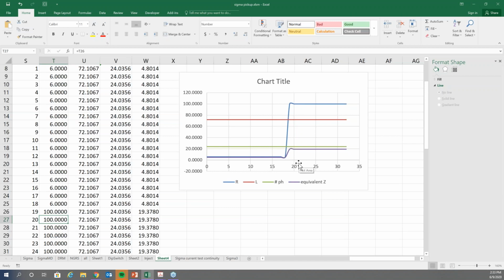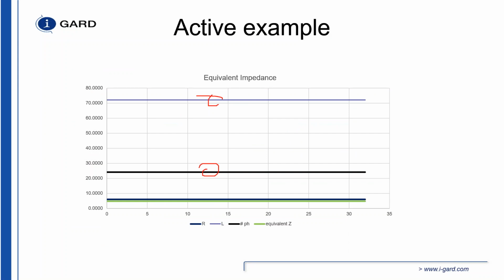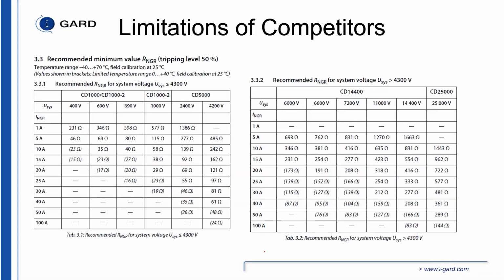Now imagine you have a 6 ohm resistor as a neutral grounding resistor, and you have an open circuit. You're looking at the absence of 6 ohms in a resistive circuit. Sometimes that's less than the tolerance of the resistors you're going to have in the sensing resistor, but because we can couple that with a frequency, we can see a significant change in that circuit. Now, we can detect resistances as low as 4 ohms. Whereas if we go to some of my competitors, without mentioning any names, their tolerance is basically 20 ohms, and they can't go up to anything above 100 amps.